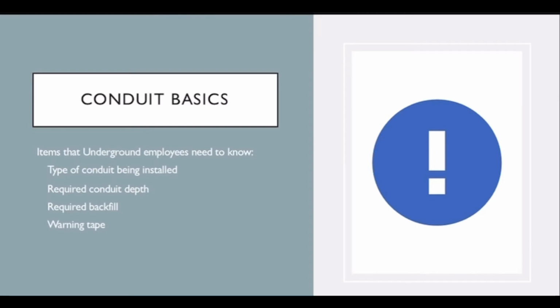Warning tape is also needed. It will be installed approximately 10 inches above the installed conduit and 10 inches of backfill. The most common type is red plastic, 2 inches wide, with 'caution underground electric below' on it. There are many circumstances where different types of warning tapes may be required and will be project specific, such as detectable warning tapes for fiber optic cables and warning tapes for communication cables, just to name a few. Your supervisor will direct you on which tape you will need to install.